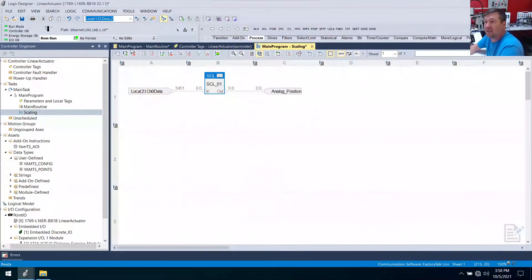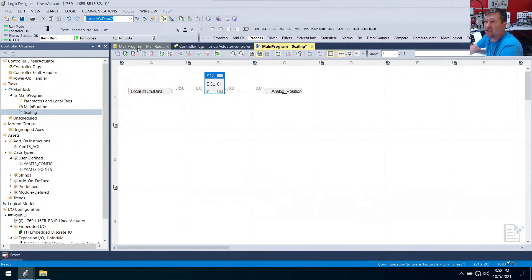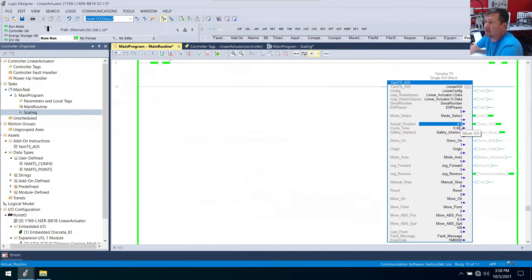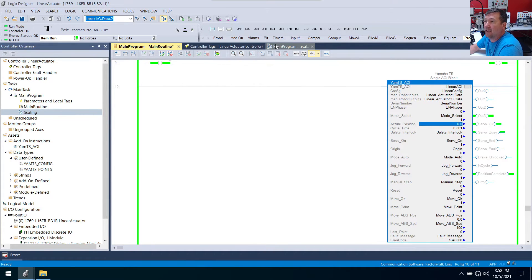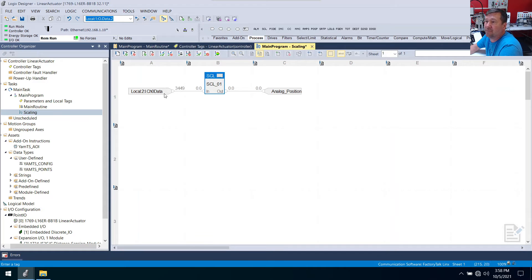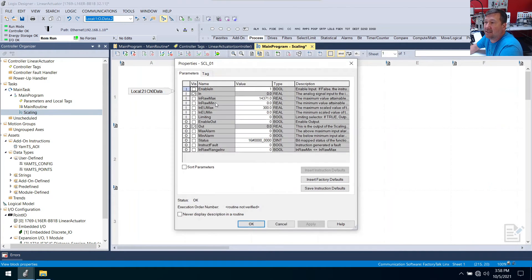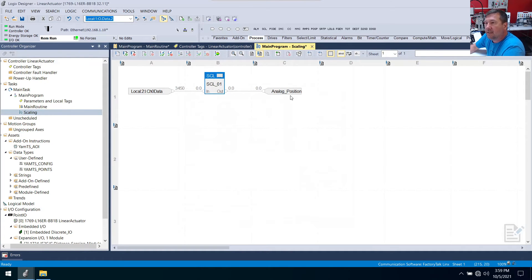So let's go over to the AOI instruction in our main routine and make sure we see that. And we are. We're at 0.0 millimeters. And our value is 3449. So that is going to be our minimum value. We're going to put 3449 and click okay.